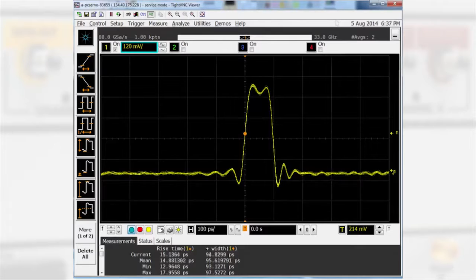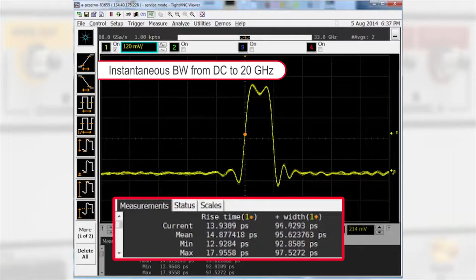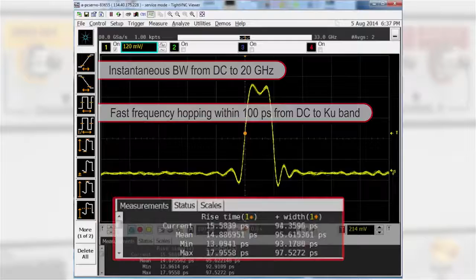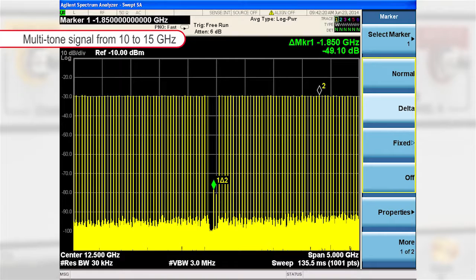If we look at wideband radar and communications, we can take wideband to the extreme. The M8195A provides an instantaneous bandwidth from DC to 20 GHz. A key benefit is the capability to do fast frequency hopping within 100 picosecond from DC to Ku band. Ultra-wideband wireless signals with any modulation scheme can be generated directly at carrier frequencies up to 20 GHz. In many cases, this saves an additional upconversion stage.